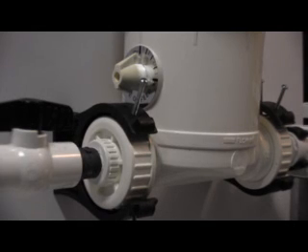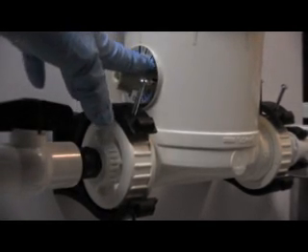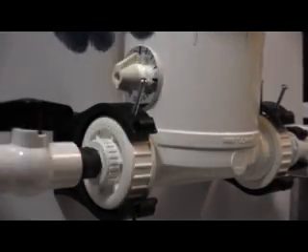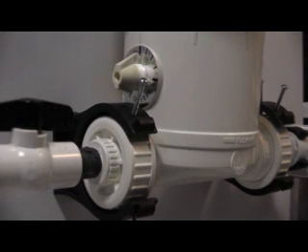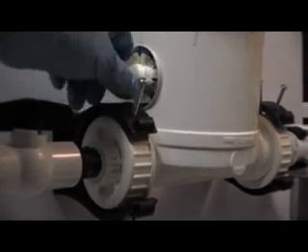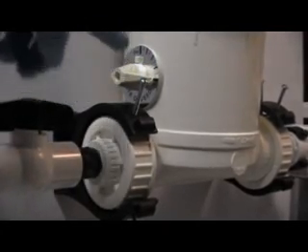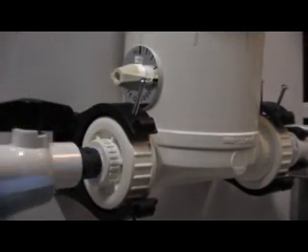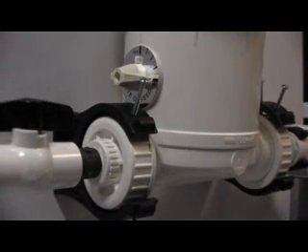So I want you to know that that dial setting, I have tested it with about 3/4 full of the tablets, the calcium hypochlorite pellets. And I found that to be here at about 2 to 3 parts per million. And here, fully open, to be 60 parts per million, maybe. Okay, maybe 60 parts per million at a continuous flow rate of about 3 gallons per minute going through here. So we're talking about 3 gallons coming in, 3 gallons going out.